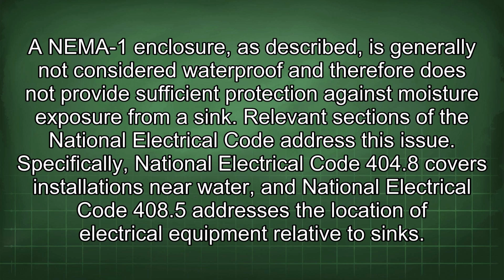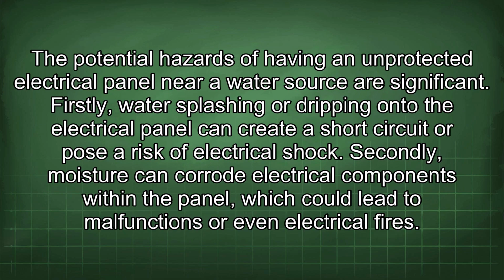Relevant sections of the National Electrical Code address this issue. Specifically, National Electrical Code 404.8 covers installations near water, and National Electrical Code 408.5 addresses the location of electrical equipment relative to sinks. The potential hazards of having an unprotected electrical panel near a water source are significant. Firstly, water splashing or dripping onto the electrical panel can create a short circuit or pose a risk of electrical shock. Secondly, moisture can corrode electrical components within the panel, which could lead to malfunctions or even electrical fires.